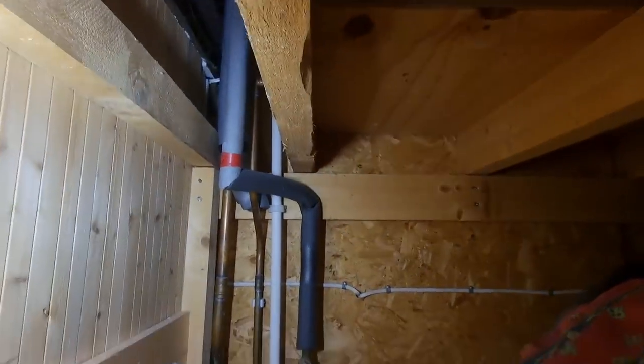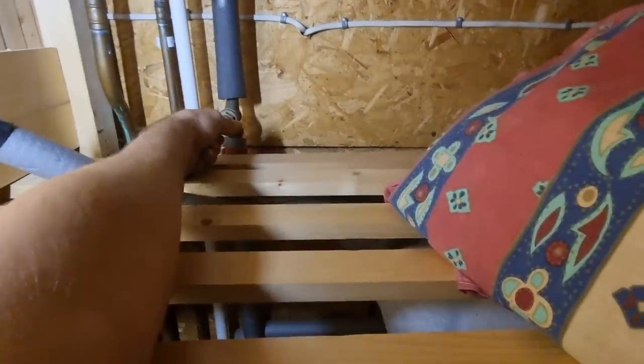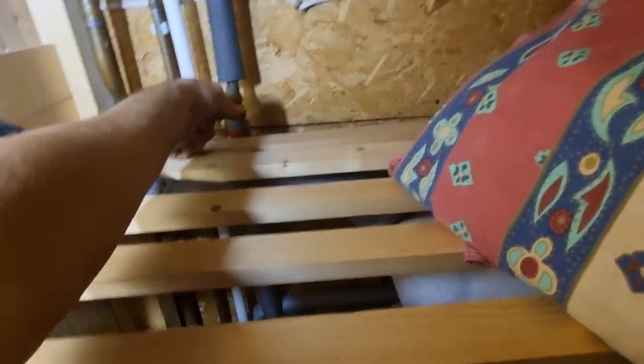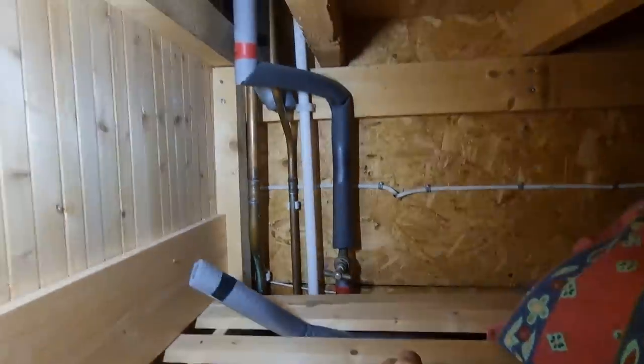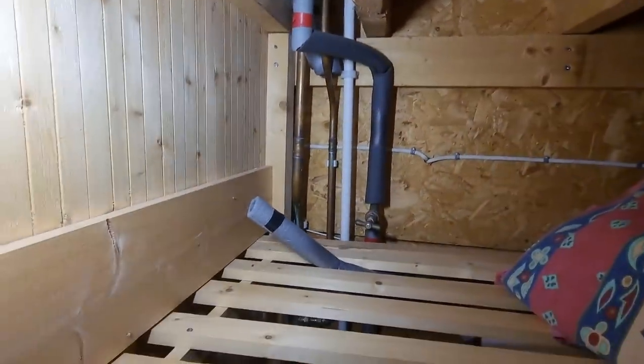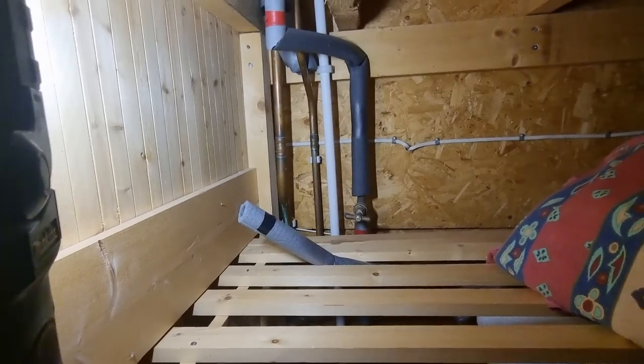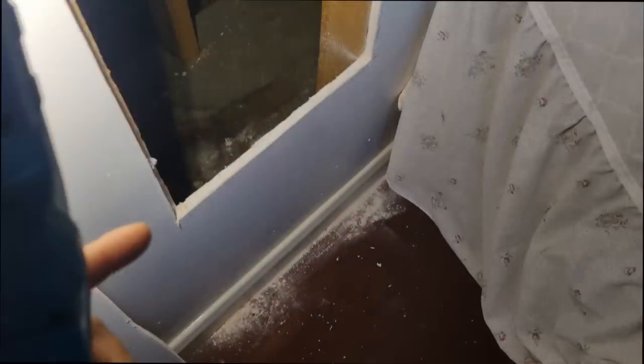So what we'll do is we'll probably knock. I'll have a look at the three-port, seems okay, but I really want to, oh, I can't turn that. I might be able to get up and bung the tank. I really want to take the three-port out, because sometimes it can collapse inside. It is the Honeywell one. We'll have a look anyway. Somebody struggled there, look. They obviously thought the tank might have been in there. That's quite recent mess, if that makes sense.